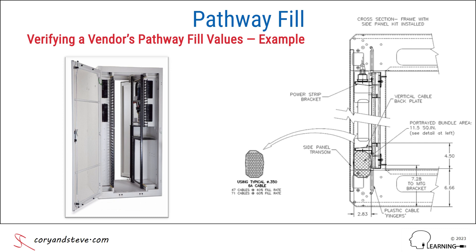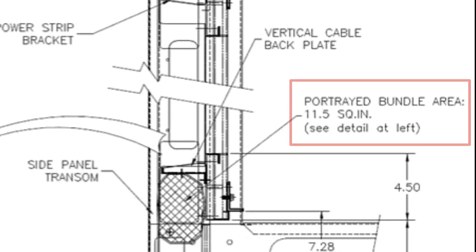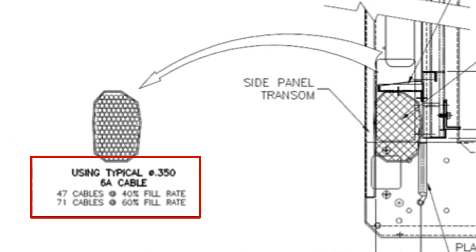As highlighted here, this vendor is giving us an 11.5 square inch pathway area and is stating that up to 47 cables with an outside diameter of 0.35 inches can be placed in the pathway at a 40% fill ratio.